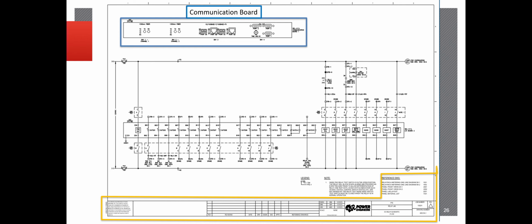Up in the top left, we have a communication board. This is a SEL-411L communication board. That's interesting. I've never seen one of those before. It is pretty much a piece of equipment that allows comms between one relay to another. In this case, it's going to be a 411L that connects to what would most likely be another 411L, whether it's at the site, but usually it's going to be somewhere else entirely on a transmission line, at the end of the transmission line. It could be connected through fiber optic cable, which is usually the most common in this day and age. It's not super expensive, it's extremely reliable, and it is extremely fast communication. There's also Ethernet, which could be utilized depending on the situation, and serial, which is very, very, very project specific.